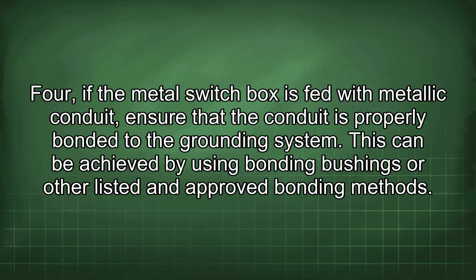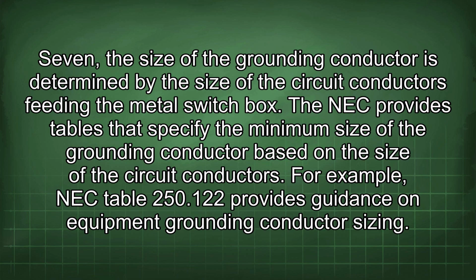4. If the metal switch box is fed with metallic conduit, ensure that the conduit is properly bonded to the grounding system. This can be achieved by using bonding bushings or other listed and approved bonding methods. 7. The size of the grounding conductor is determined by the size of the circuit conductors feeding the metal switch box. The NEC provides tables that specify the minimum size of the grounding conductor based on the size of the circuit conductors. For example, NEC Table 250.122 provides guidance on equipment grounding conductor sizing.